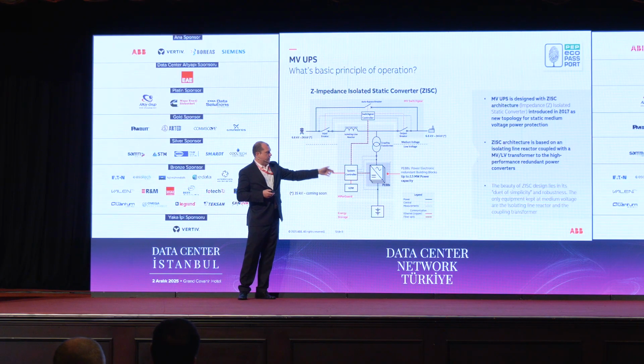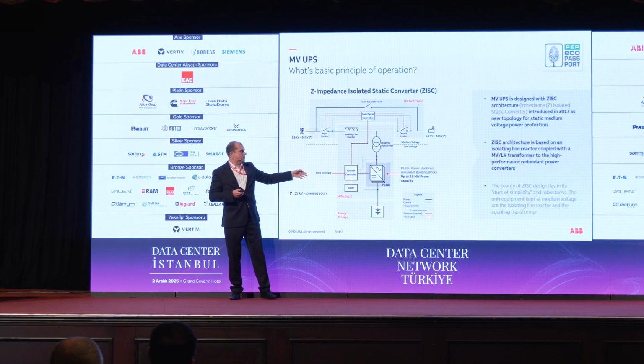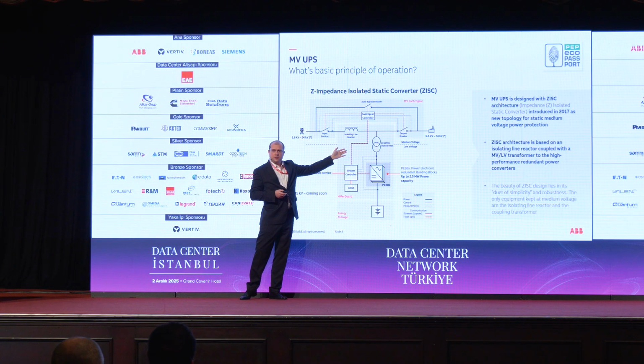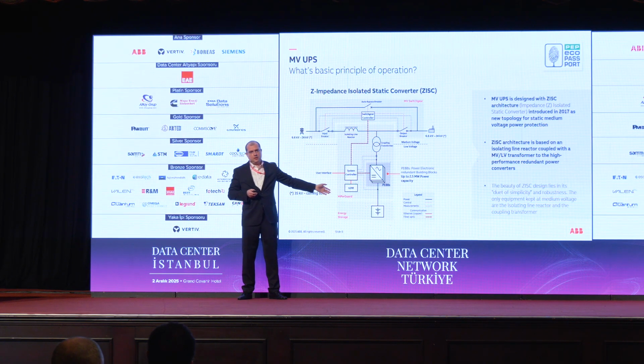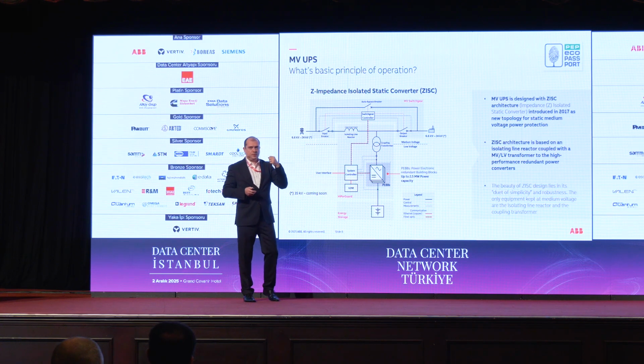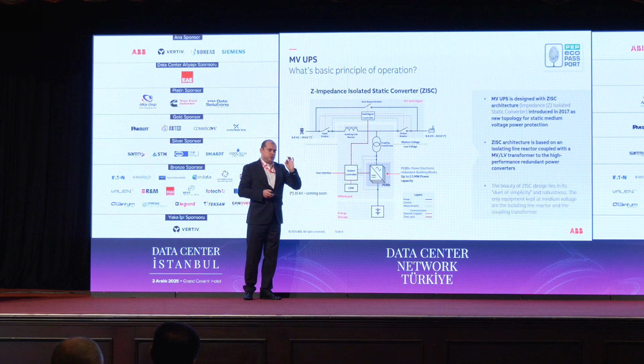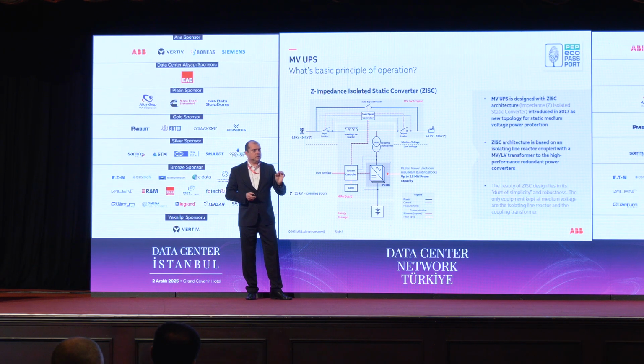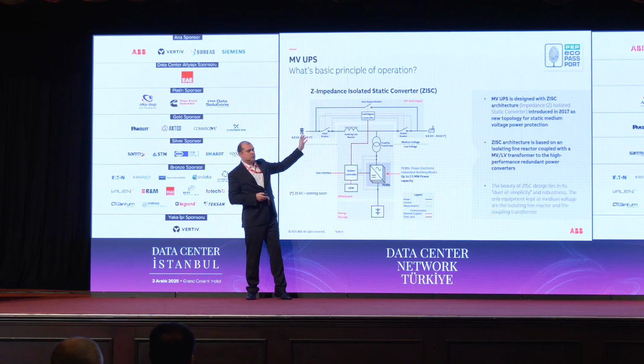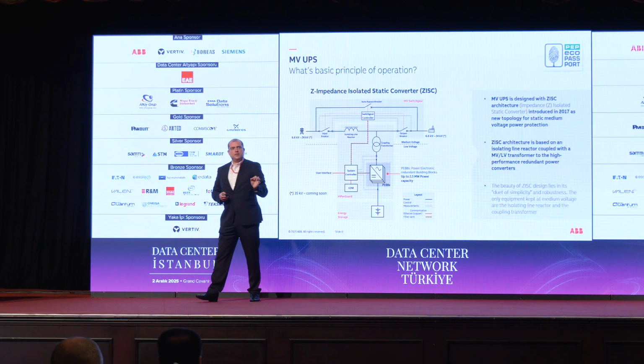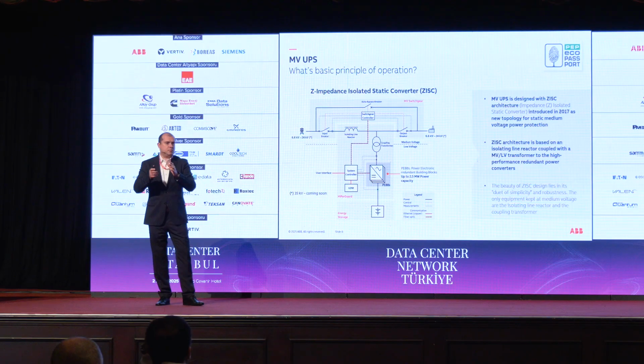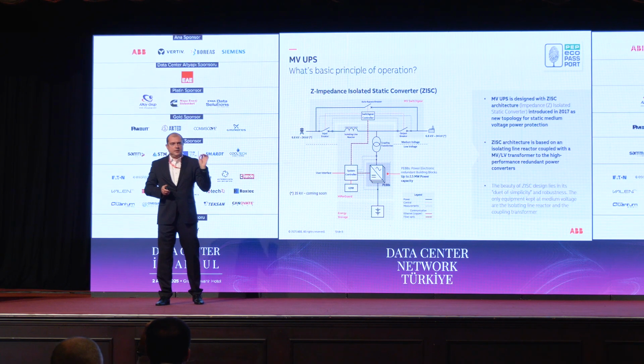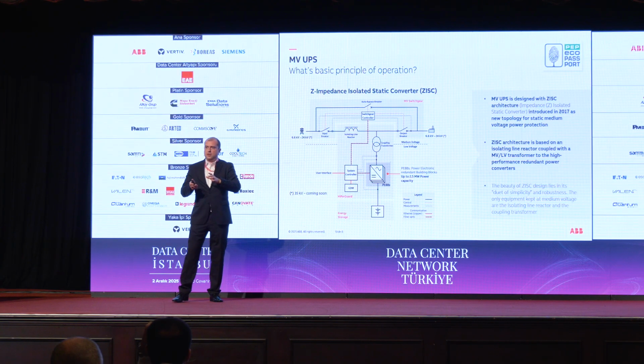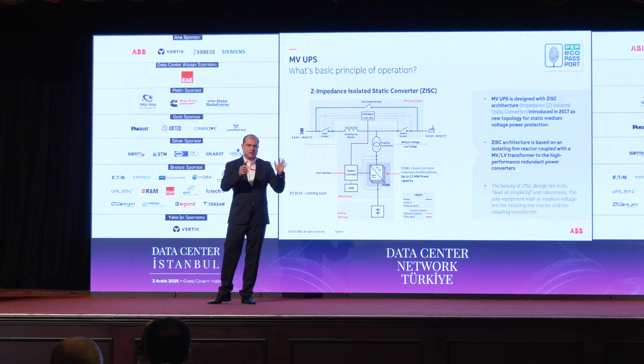In this gray area, this is the indication of the medium voltage UPS, consisting of a line reactor, or choke, step-up, step-down transformer, and power converters. Coupled with this is also the energy storage, in our case based on lithium-ion systems, to be robust. And what is novel is that this UPS has the automation and functionality together with the switchgear. We always knew low voltage UPSs as systems that work in harmony with the batteries. In this case, the UPS works in harmony with the batteries, but also with the switchgears. This is a triplet that is being reinforced by state-of-the-art automation.